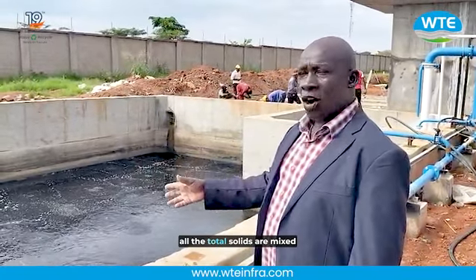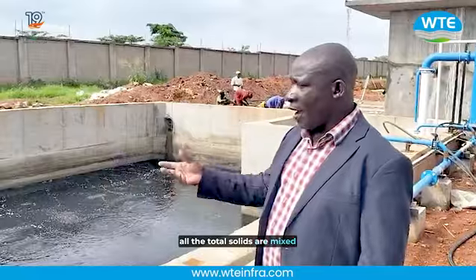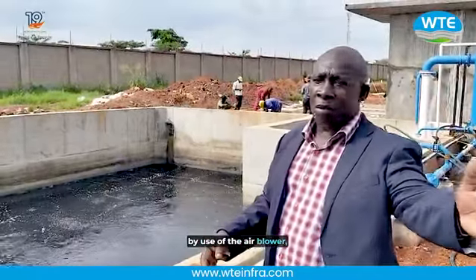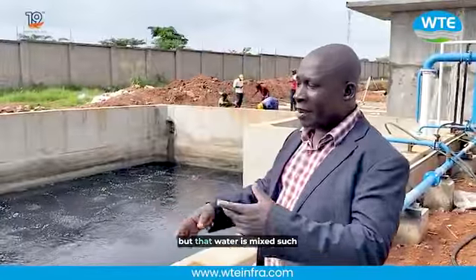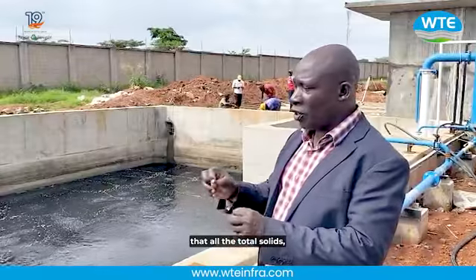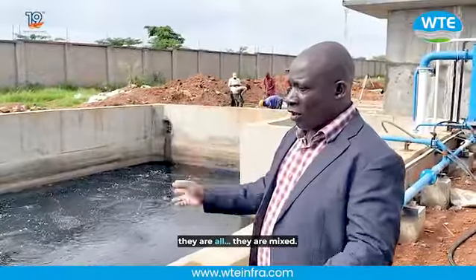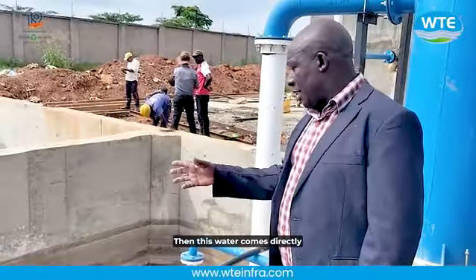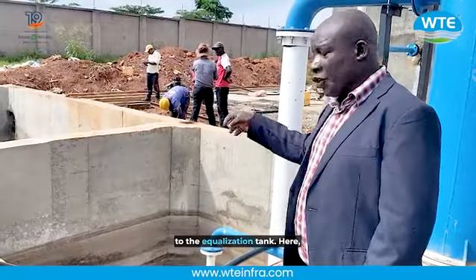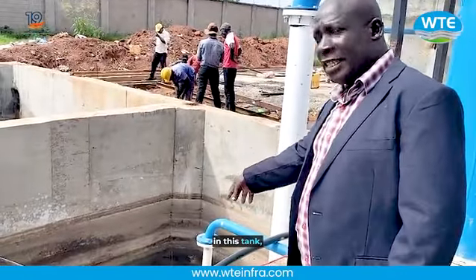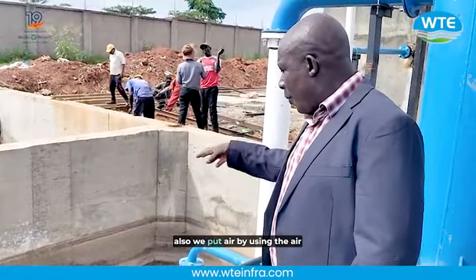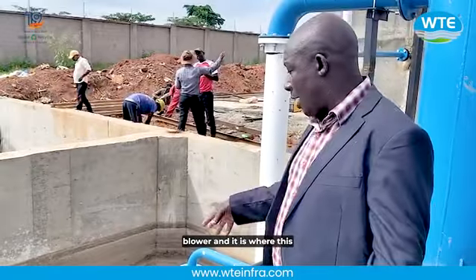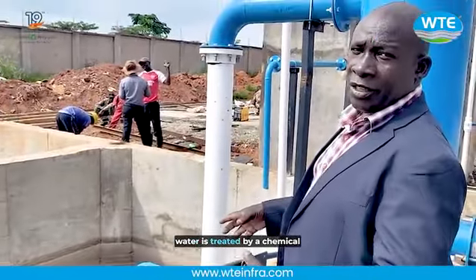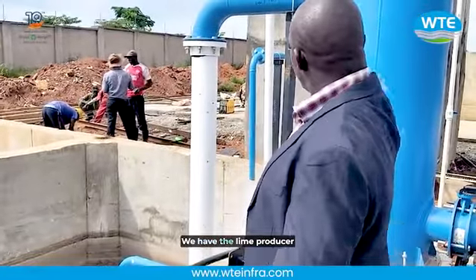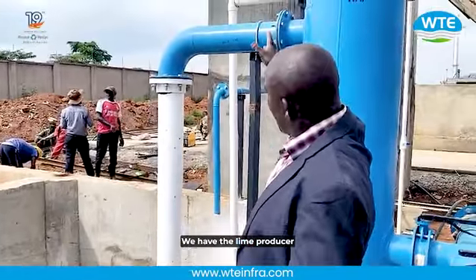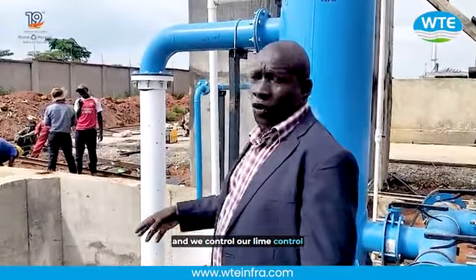In this tank, all the total soluble solids are mixed by use of the air blower, as you are seeing. It is like boiling, but that water is mixed such that all the total soluble solids are mixed. Then this water comes directly to the neutralization tank. Here in this tank, we also put air by use of the air blower, and it is where this water is treated by a chemical called lime. We have the lime tank, and we use lime to control pH.